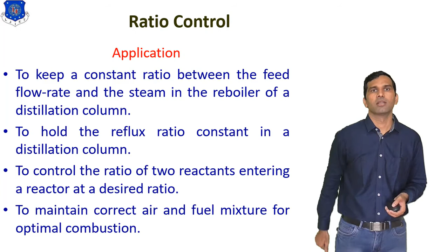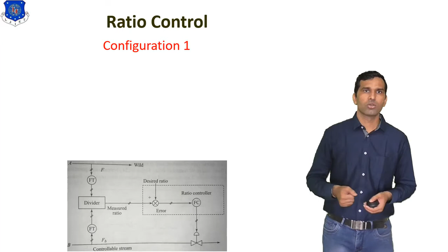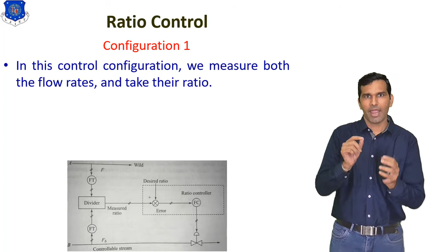Now we discuss how it works. By using these configurations, we understand the working of this ratio control system. The ratio control system can be used in different ways. First we understand what we have named configuration 1. Here you can see in this control configuration, we measure both the flow rates and take their ratio. This ratio is compared with the desired ratio, that means our set point as shown in the figure, and the deviation between the two is used to generate the actuating signal for the ratio control.